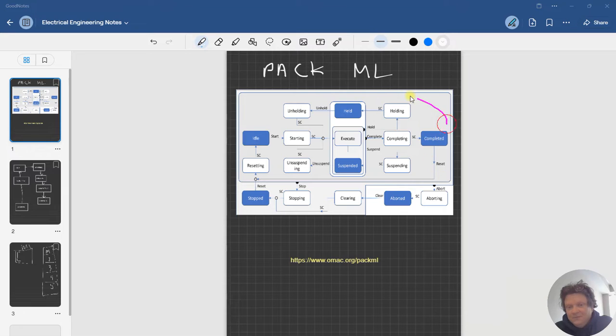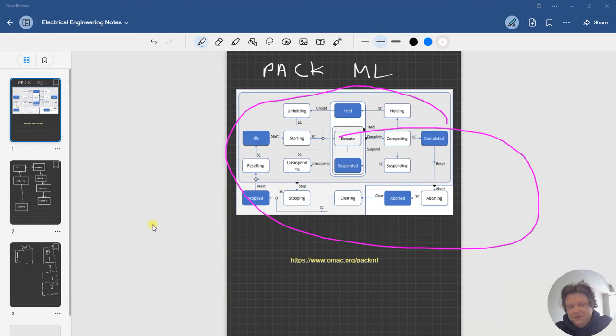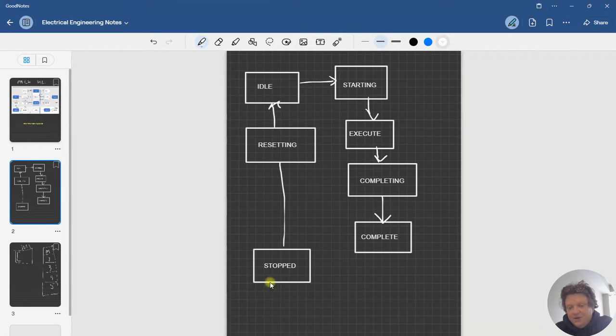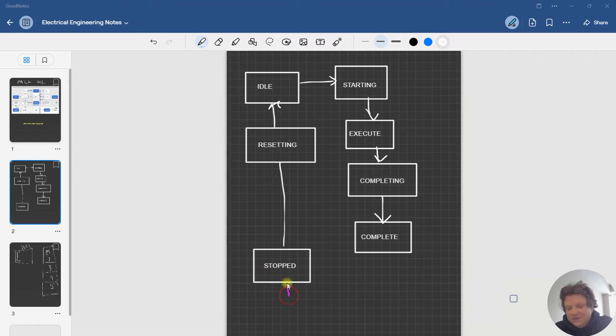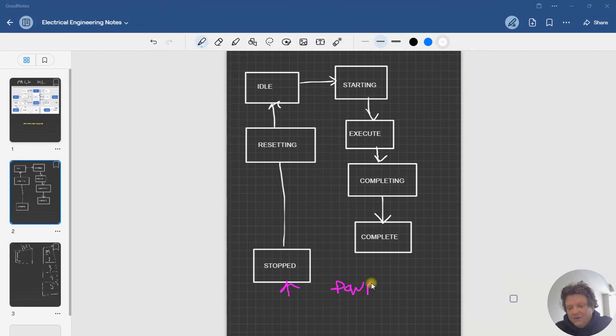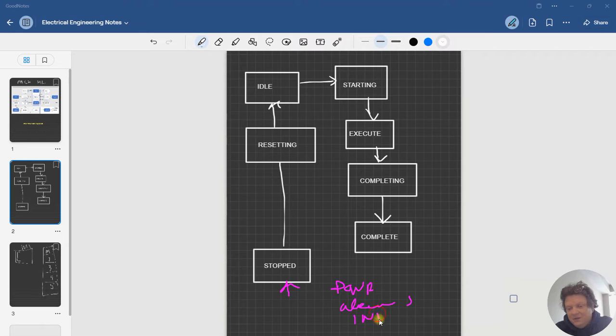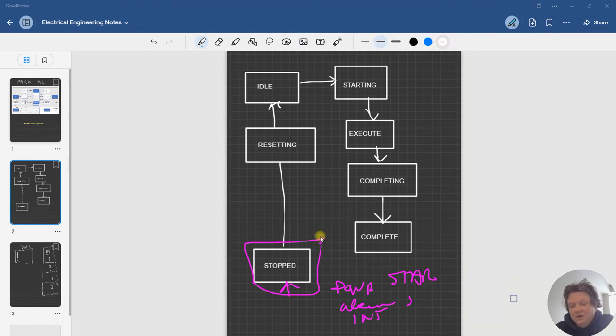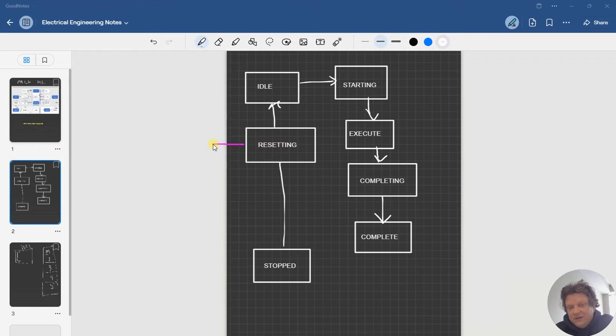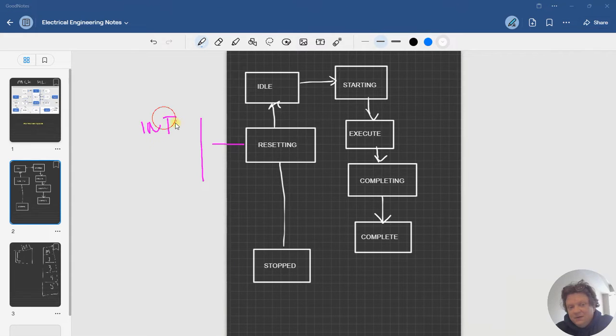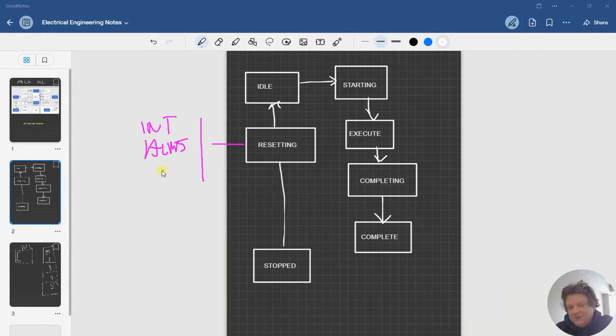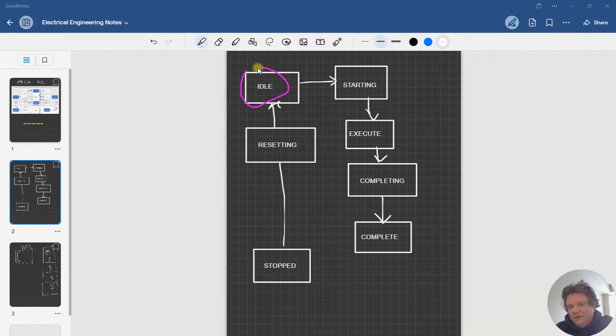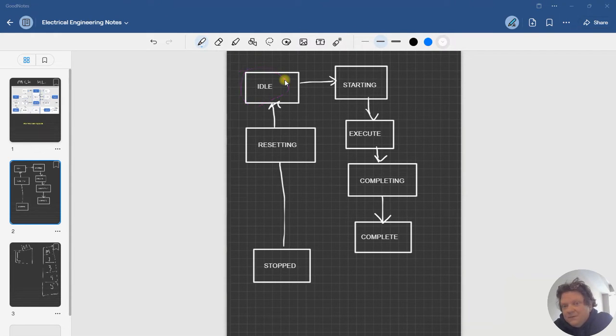what do I have to do or what is my state when I'm stopped? Obviously we don't have control power, we may have alarms, none of our interlocks are made. We haven't hit the start button, so we are in a stopped state. Some of these things we come in as reset. If we clear our interlocks, clear our alarms, and set the machine up so that it's ready to go, are we reset? Yep. Okay, then we go to idle.